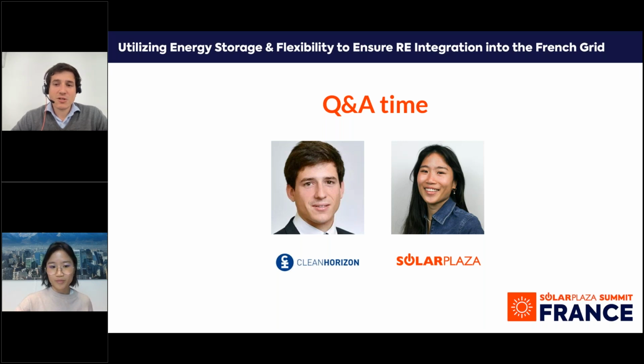That's a very relevant question. For FCR, as a reminder, you're looking at about 0.8 megawatt-hour per megawatt. For aFRR, you're probably looking at more like a 2-hour discharge duration, meaning you'd need a 1 megawatt, 2 megawatt-hour storage system to participate. There's also some power oversizing, so you need to derate your installed capacity, but essentially you need a 2-hour battery to participate.